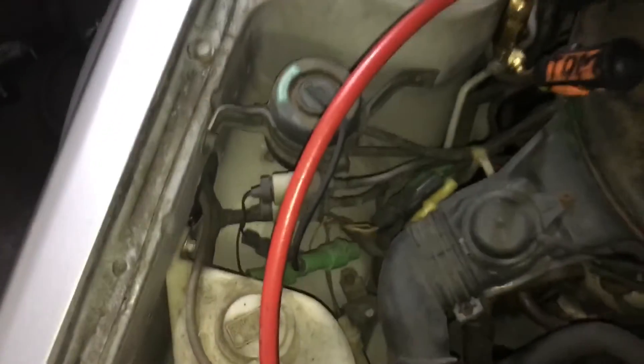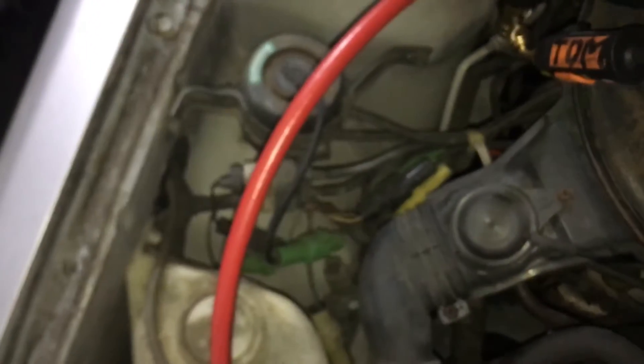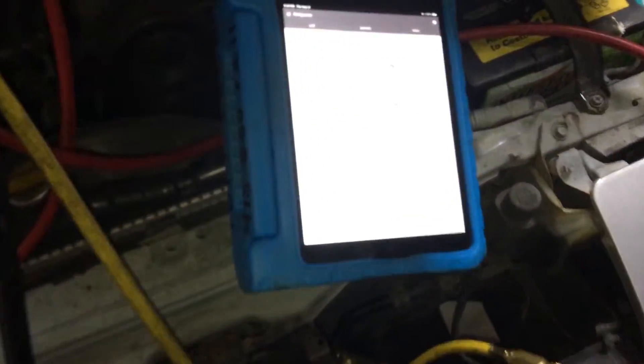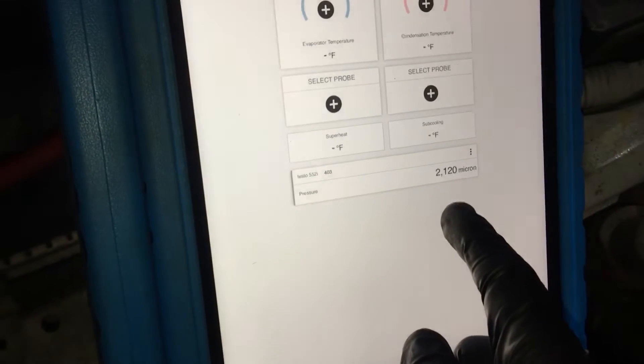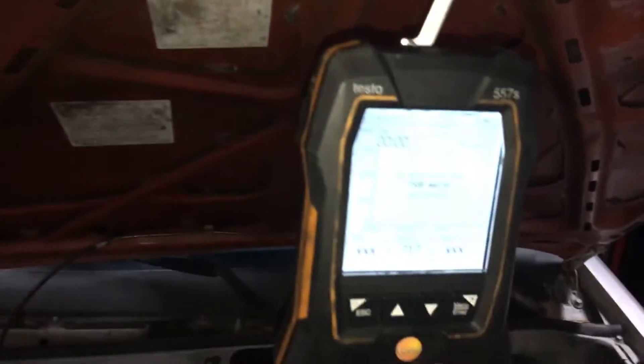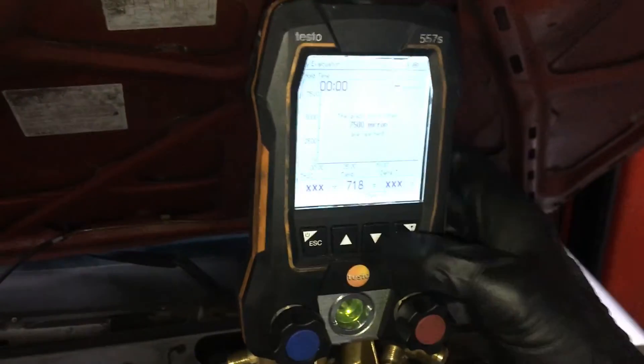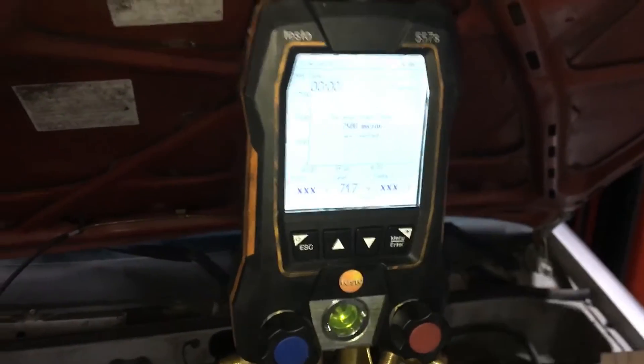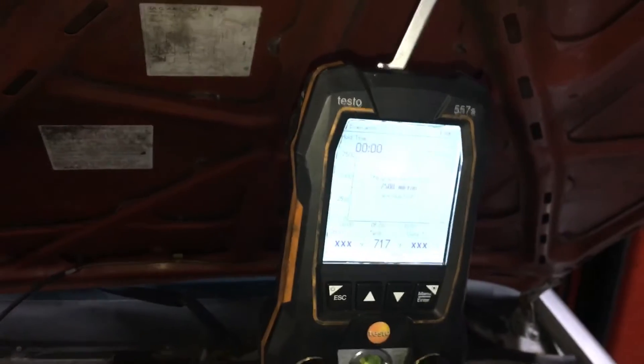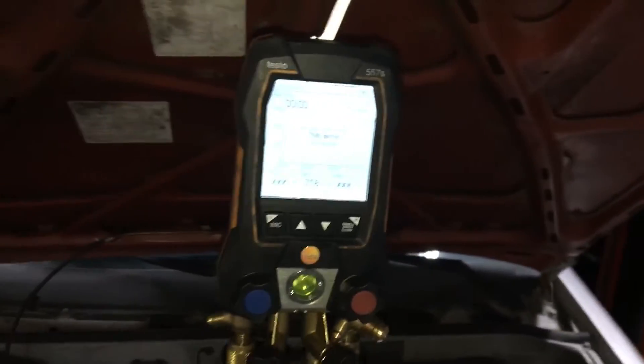I'm hooked up over there. I'll turn that back on because I'm down at 2000–2500 microns. So I'm way below 7500 microns, but nothing's happening.